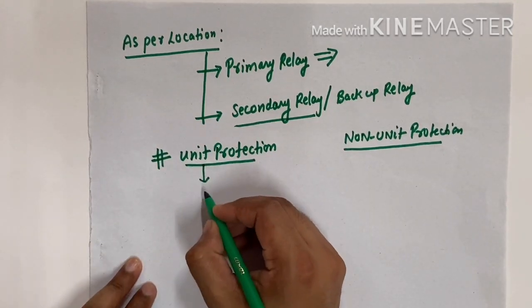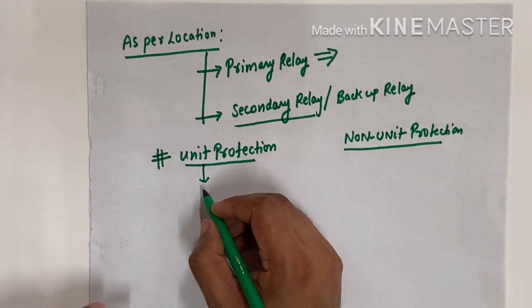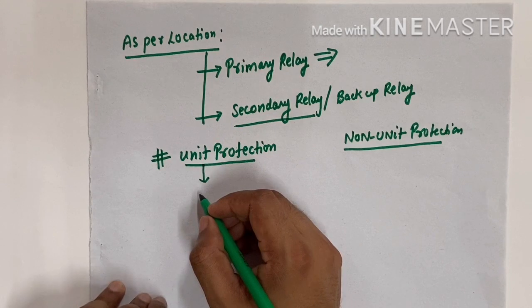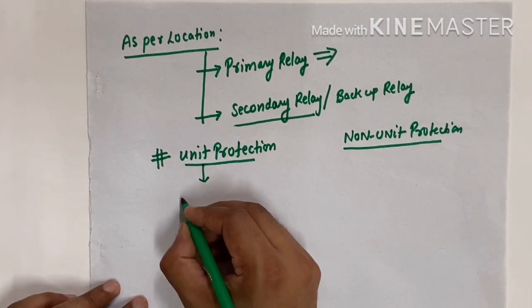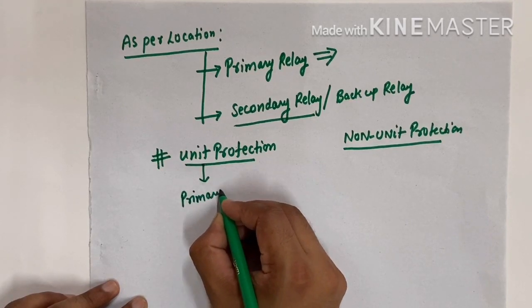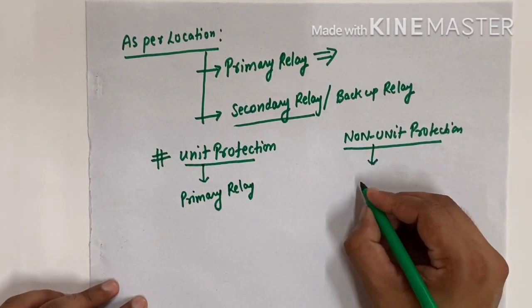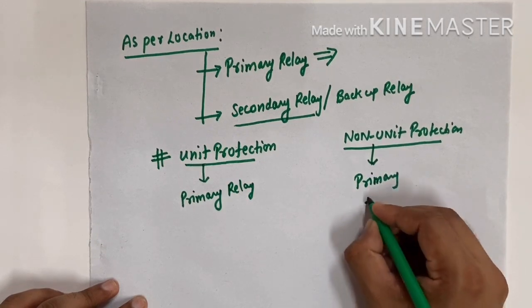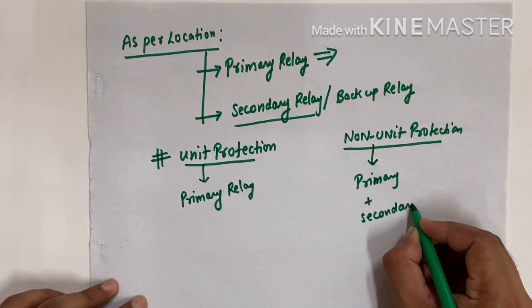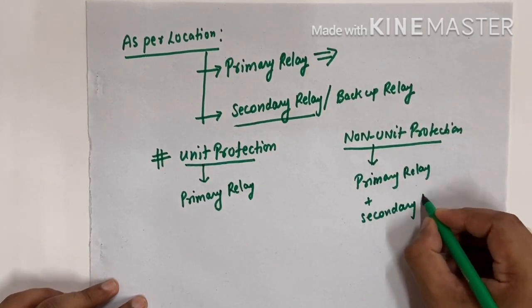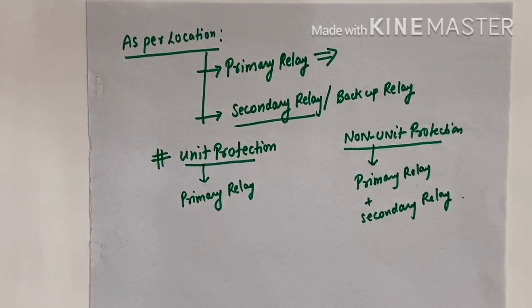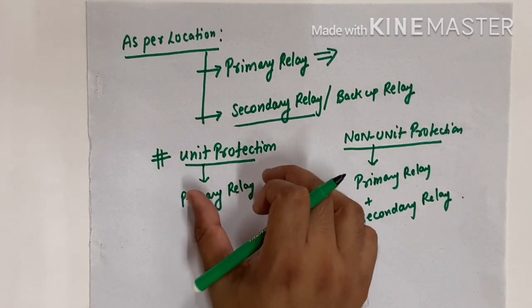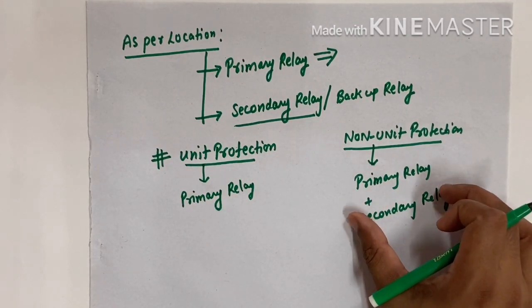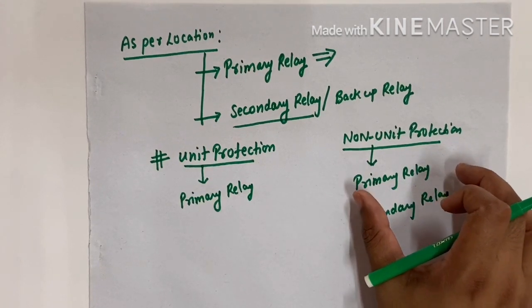Unit protection means the protection system consists of primary relay only, then we call it unit protection system. If the protection system consists of primary relay plus secondary relay, then we call it non-unit protection.